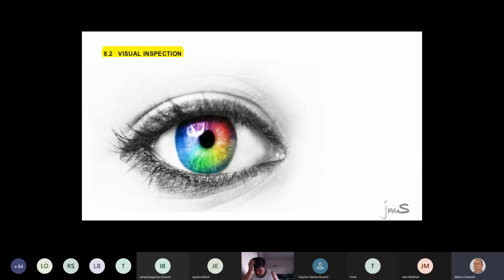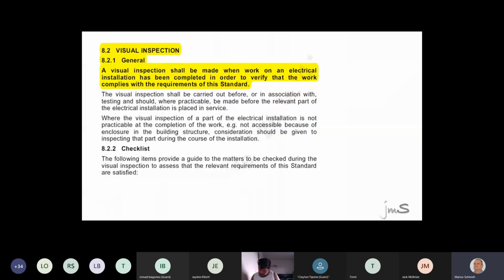What instrument will you use to do a visual test? A Megger, insulation tester, a multimeter, or an eyeball? It's in the exam. They could ask you. They just want to know if you know what we're talking about. Oh, that will be an easy one, but you're going to say insulation tester. Okay, guys, when you do a visual inspection, please make sure that the visual inspection is per the legislation. Visual inspection in the 3000 book says, look at this, look at this, look at this.